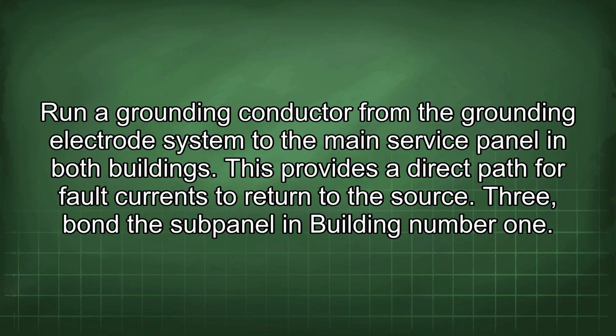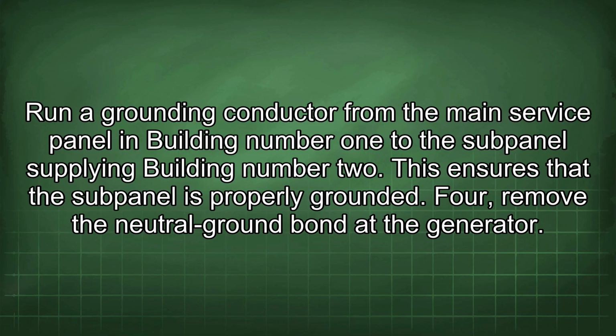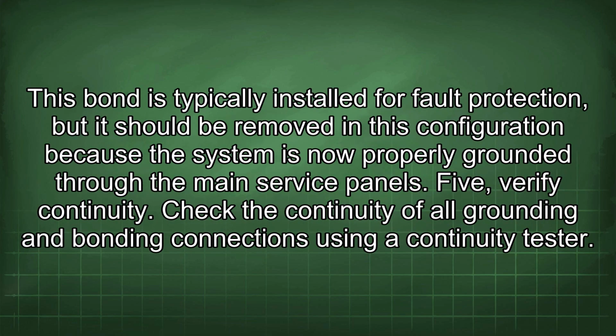3. Bond the subpanel in building number 1. Run a grounding conductor from the main service panel in building number 1 to the subpanel supplying building number 2. This ensures that the subpanel is properly grounded. 4. Remove the neutral ground bond at the generator. This bond is typically installed for fault protection, but it should be removed in this configuration because the system is now properly grounded through the main service panels.